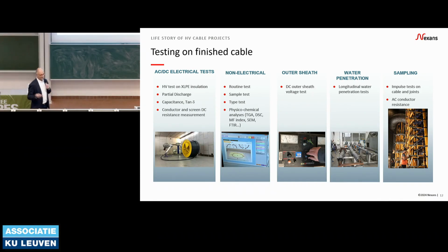A lot of tests: electrical test, non-electrical test, electrical characteristics, physical characteristics, water tightness characteristic. If you have a cable, even the ground is tested for water tightness. And of course when you make it subsea, the conductor itself is watertight, and you need that as well. Then you have some sampling tests like impulse, so you make a lightning strike on your cable system, cables plus accessories, to check that everything is fine.